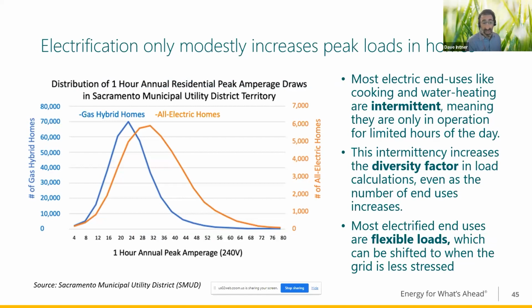A couple of quick points on how all-electric homes have a higher usage and a slightly higher peak than hybrid homes, but it's moderate. Sacramento Municipal Utility District did a study of about 100,000 homes, comparing mixed-fuel homes to all-electric homes, and didn't see a significant increase in peak amperage. Even the highest-demand homes, in terms of their one-hour peak, none of them exceeded 80 amps. This comes from the fact that most of these end uses have a high diversity factor, meaning they're not all on at full power at the same time.